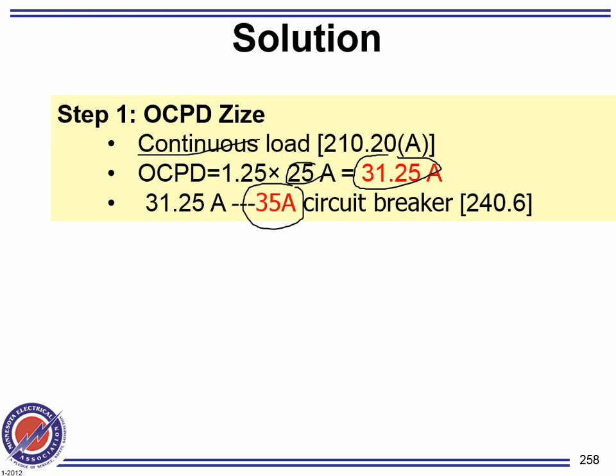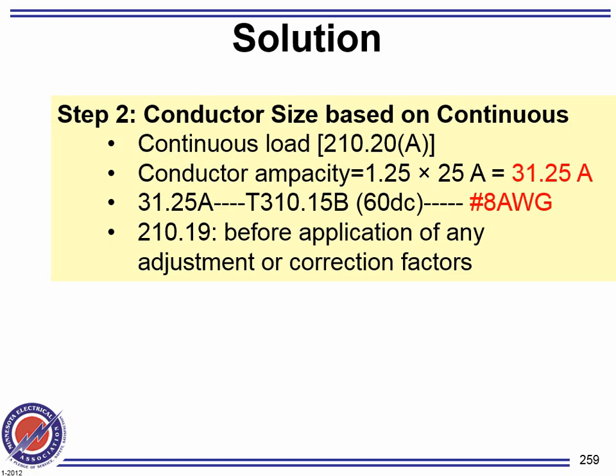No, not common. But on the test, you go by 240.6. Yeah, go by 240.6. Okay, so we found the breaker. Now let's go size the conductor. To size the conductor, guys, for continuous load we multiply by 1.25, so that gives me this amount.